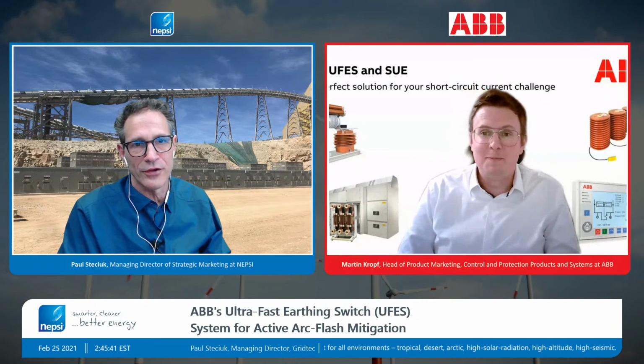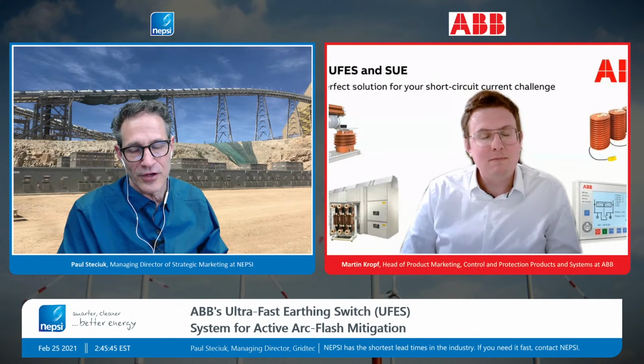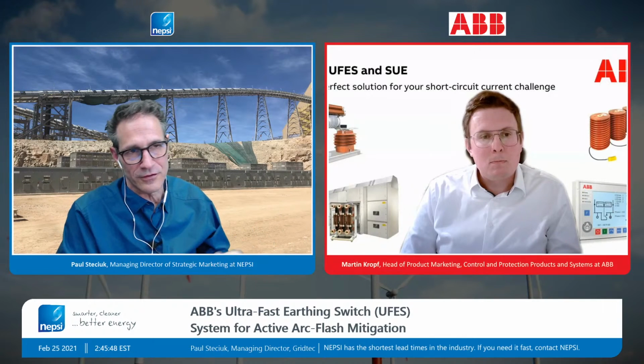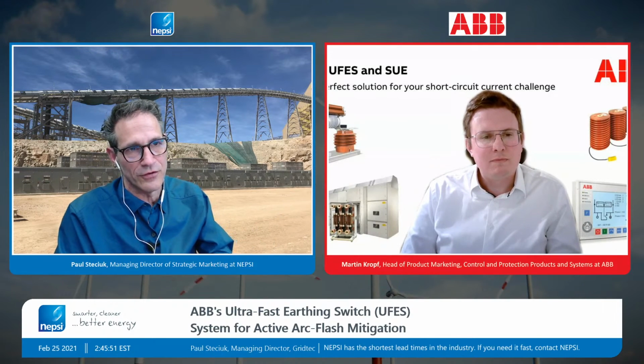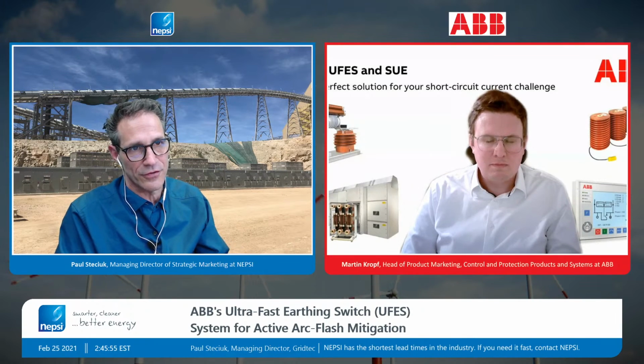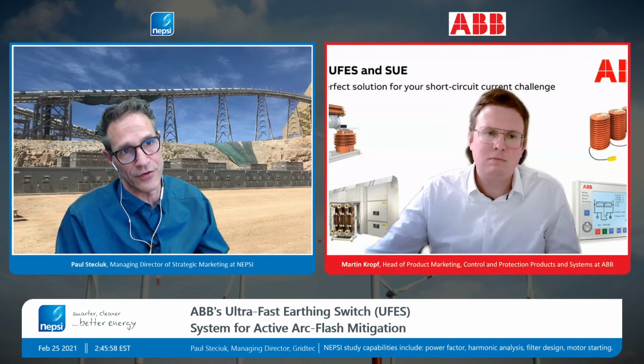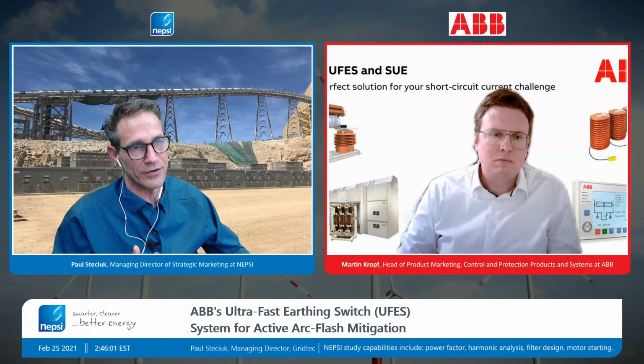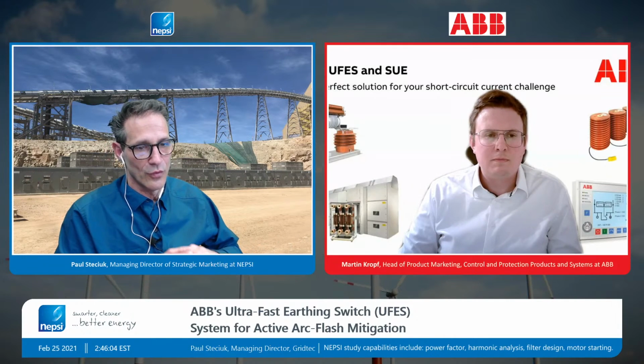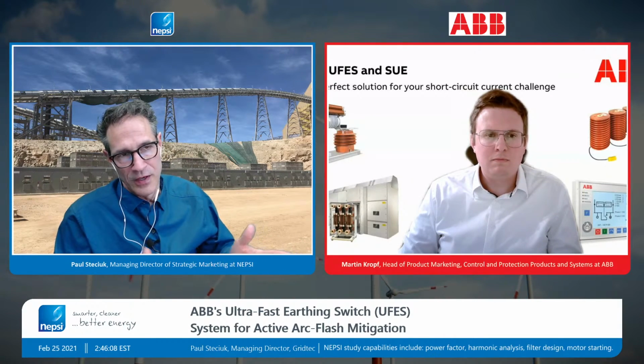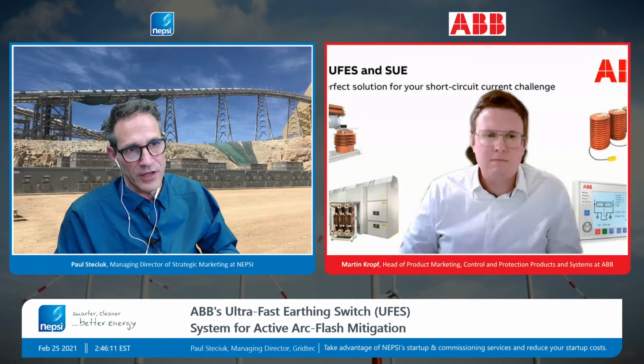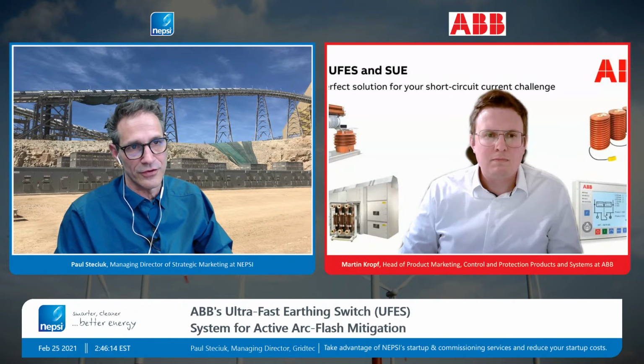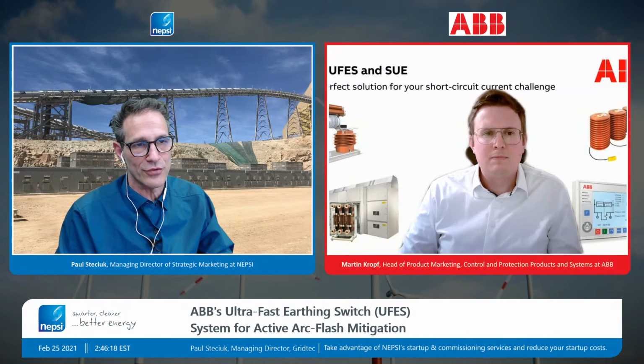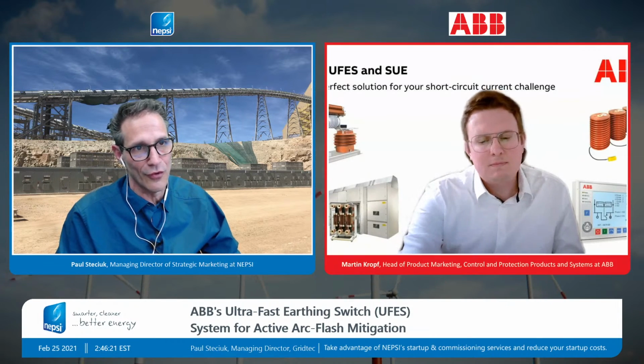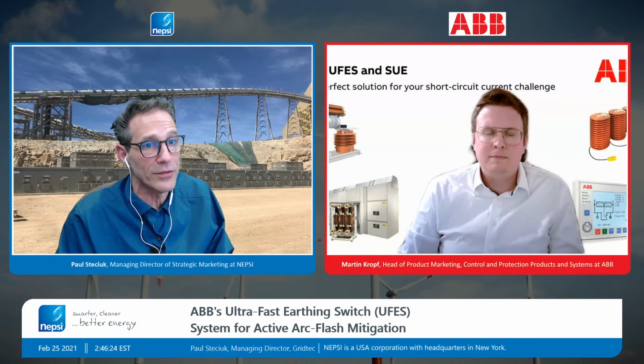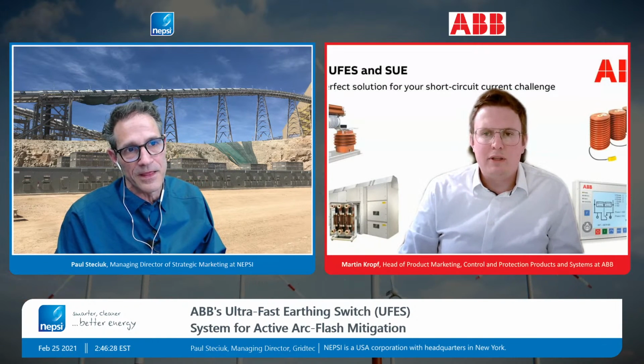Please. It's a question regarding coordination and trying to limit the extent of the fault. The reality is that this UFES system creates a three-phase bolted fault. You're bringing that bus voltage down to zero. And whatever is connected on that main bus switchgear line-up and downstream from there will see 0 volts and will trip offline. So the reality is that you're trying to prevent damage. You're going to have a shutdown in your loads, and whether you trip those other breakers in the differential zone or not really doesn't matter, because all the load will drop off because of the interruption. No, absolutely, yeah.